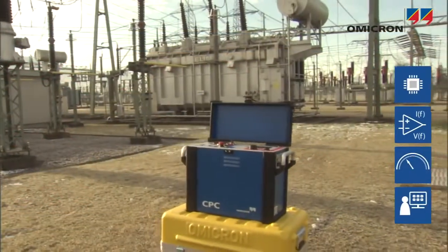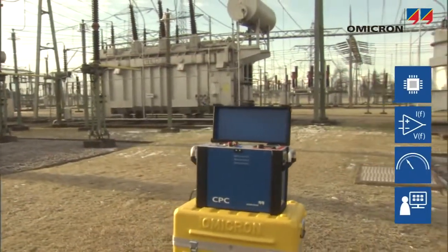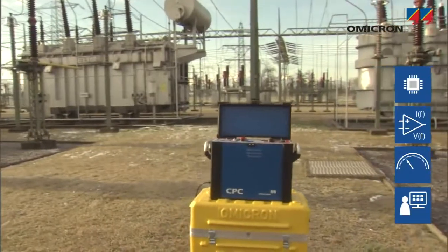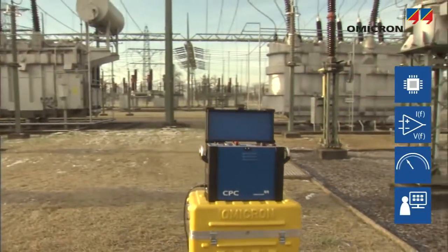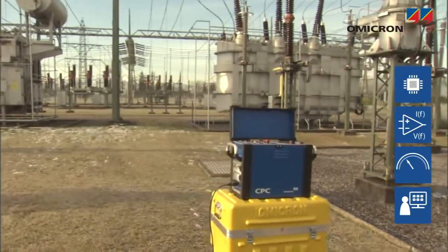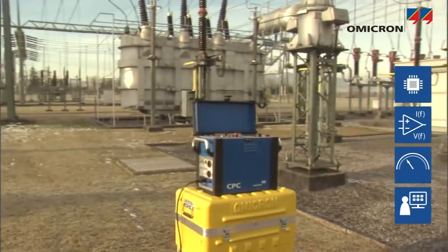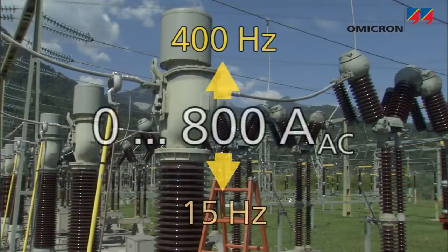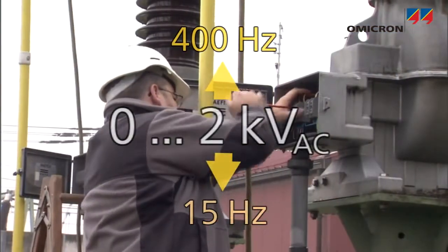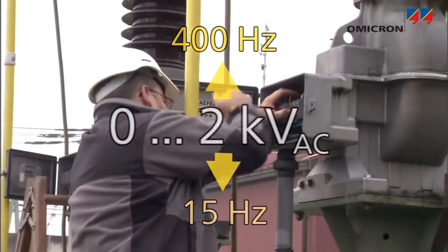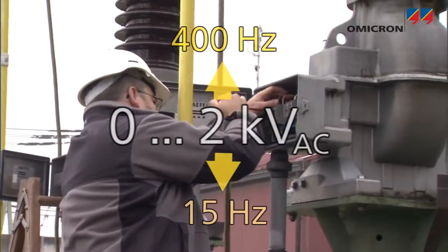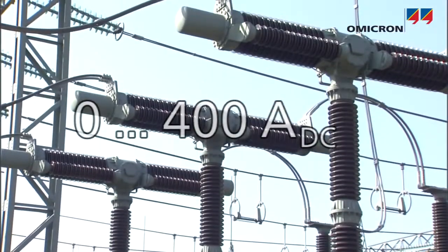The same technological basis is used in the CPC 100, a powerful multifunctional primary test set for substation commissioning and maintenance. It can generate up to 800 amps AC and up to 2000 volts AC at frequencies ranging from 15 to 400 Hz and up to 400 amps DC.